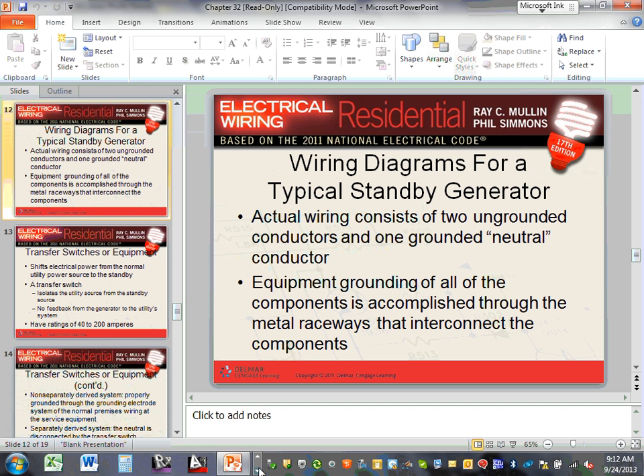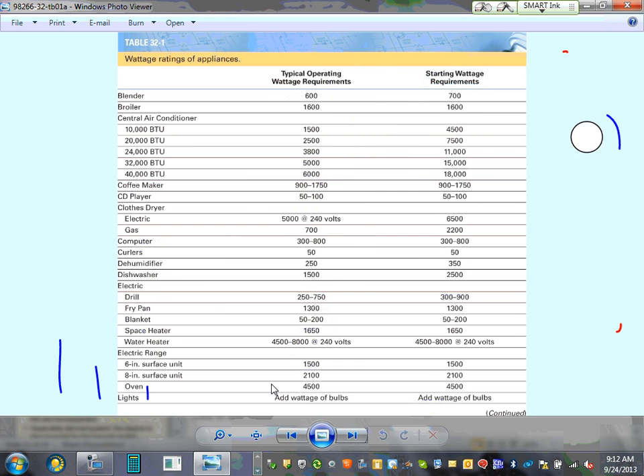The last thing I want to talk about, guys, is how do you size for what size gen you want? Generators are sized in kW and voltage, guys. So I told you 5, 7.5, and 10. What size do you want? 7.5, Chad? How do you reach the size? Here's how they size a generator, guys. They size a generator based on two factors.